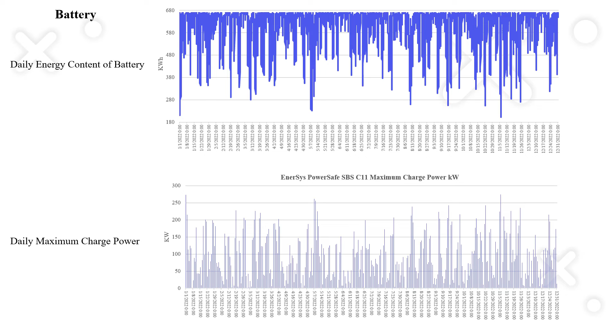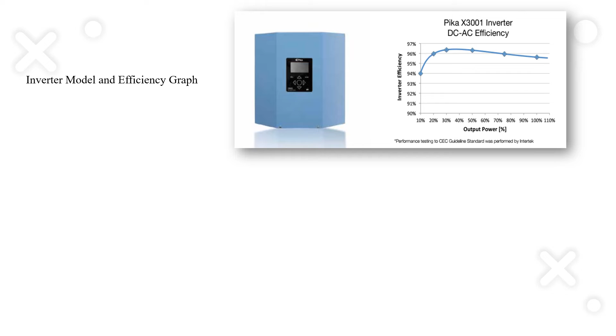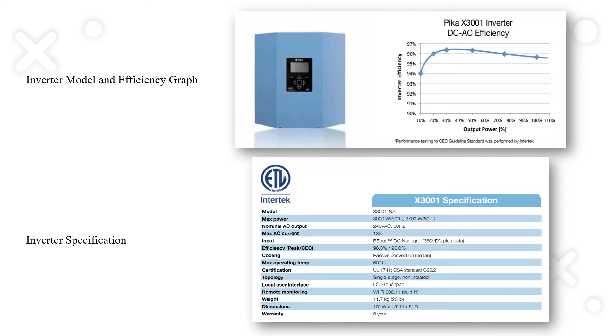For this project, we also need an inverter. You can see the shape of this inverter and also its efficiency graph. It means that whenever it has 30% output power, it can have efficiency between 96 to 97%. Also in this table, we can see the inverter specifications. For example, its model is X3001, the maximum power is 3000 watts, nominal AC output is 240 VAC, and max AC input current is 13 ampere.